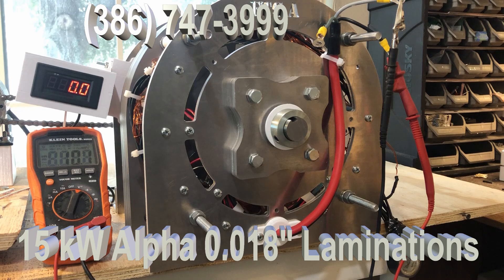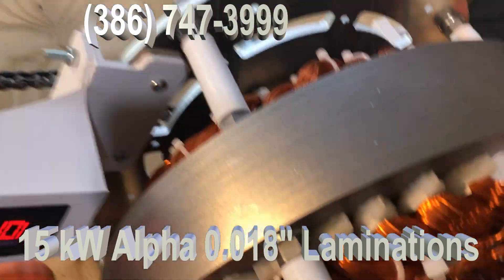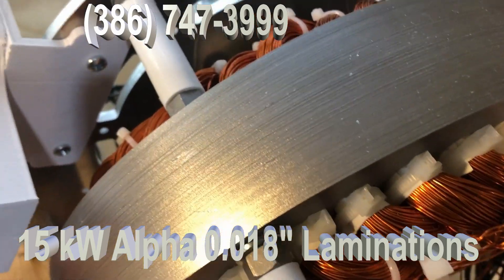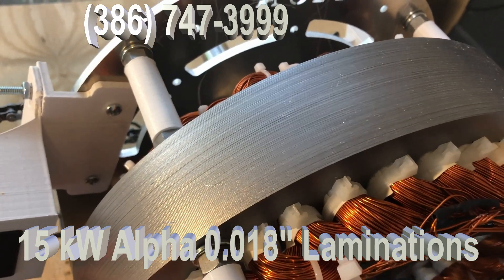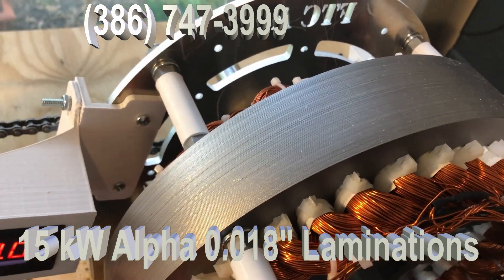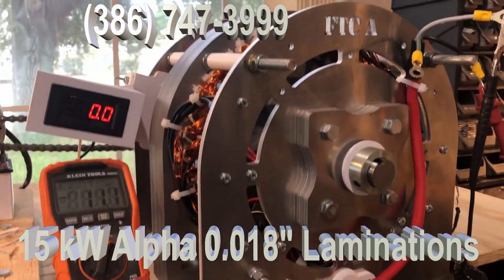The key to this generator and what makes it unique is we redesigned how the coils fit in the generator. But the most important thing we did was change the laminations. Now if you look here, these laminations are not the original laminations — these are 0.018 inch thickness.